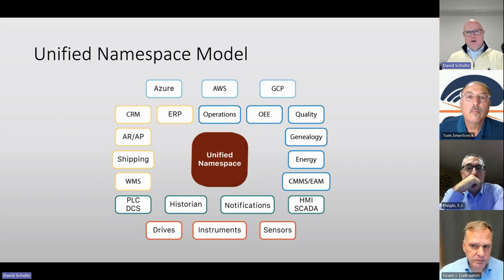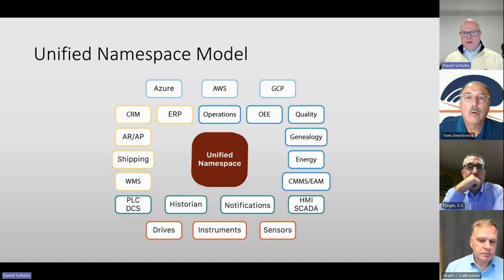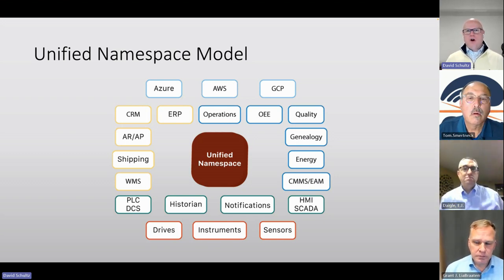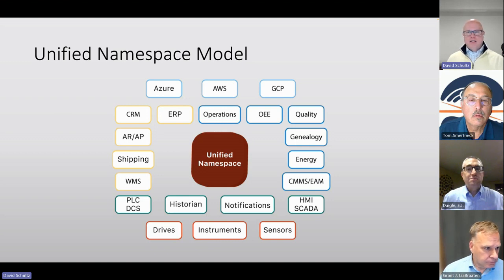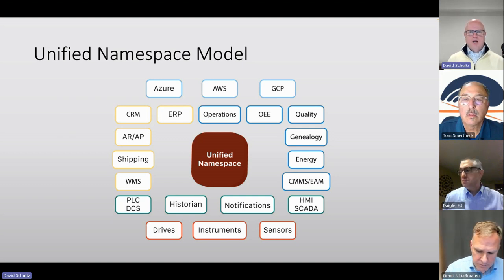As you start integrating with tags that exist in PLCs, this is really one of the easiest things to do. We typically start off modeling assets because that's the most readily consumable and understood within a unified namespace. So that PLC tag is going to be based there. No longer being that temp 6243 or whatever number I made up earlier, that's now going to be my filler temperature in nozzle 6 in my overall hierarchy. I'm in this plant, this area, on this particular line, in this particular unit, and that's now going to be my temperature. You'll understand what that is.